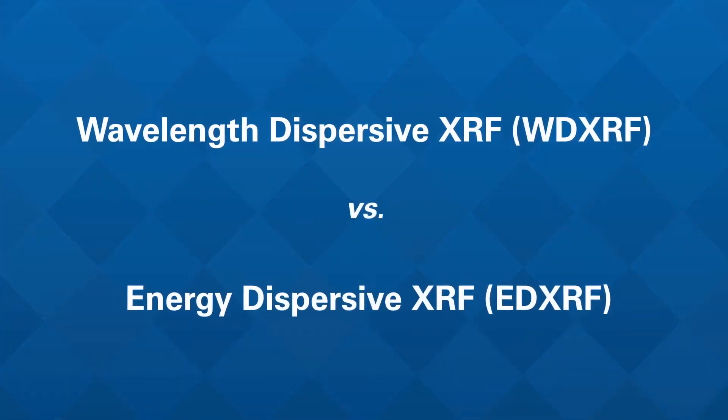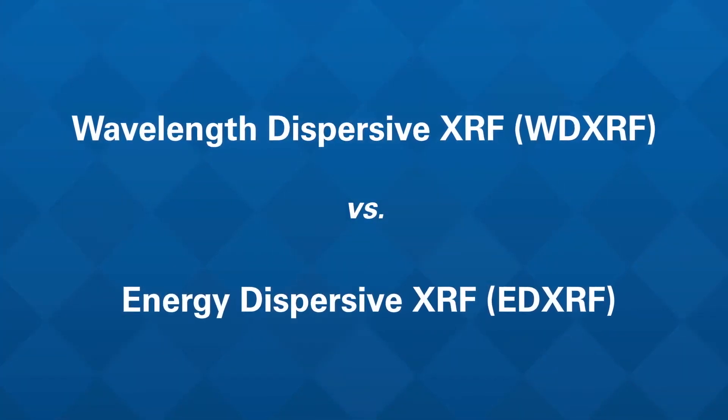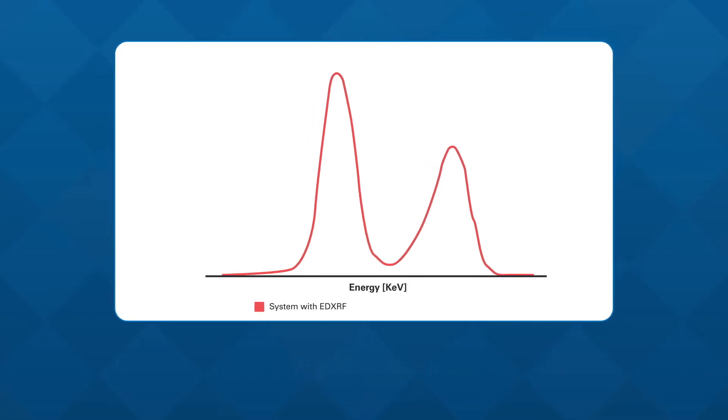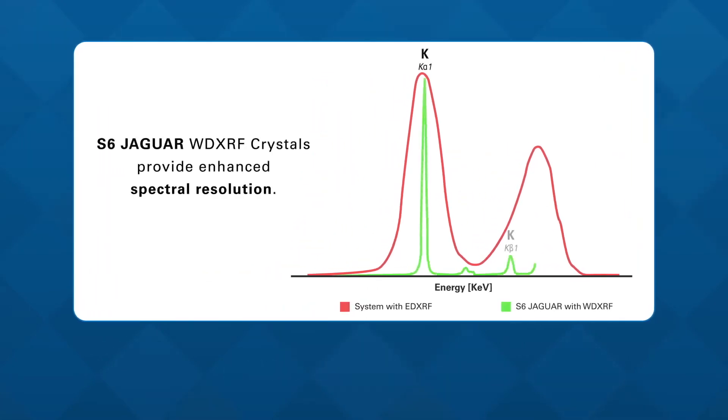But how does the S6 Jaguar Wavelength Dispersive XRF compare with energy dispersive XRF? When measuring complex samples, here we see that the energy dispersive has delivered broad spectral resolution. Thanks to its optimal analyzer crystals and detectors, the S6 Jaguar provides better spectral resolution.